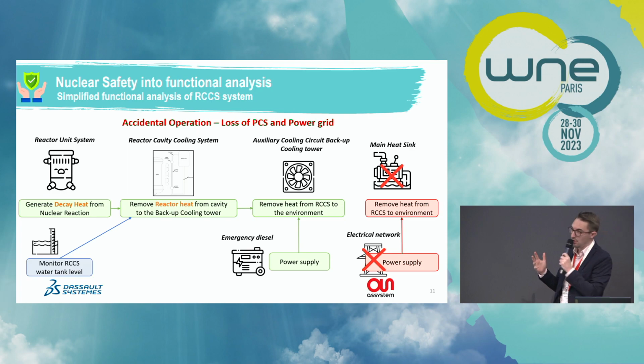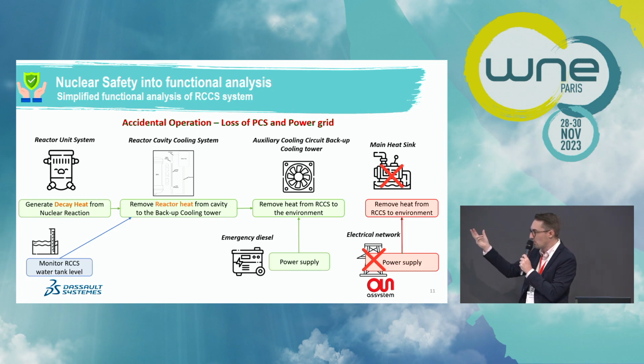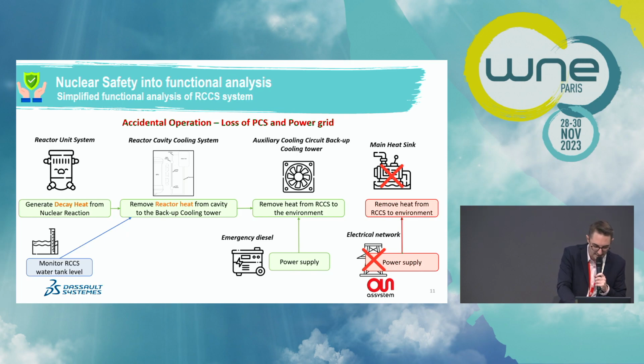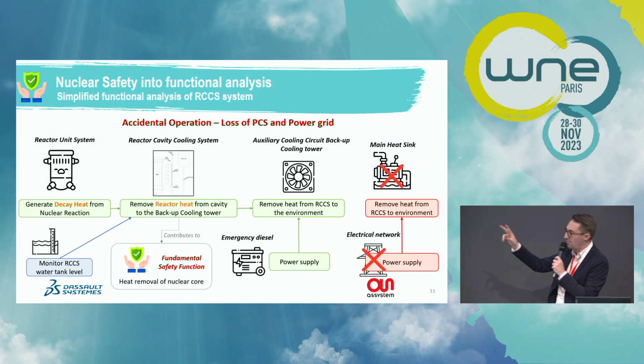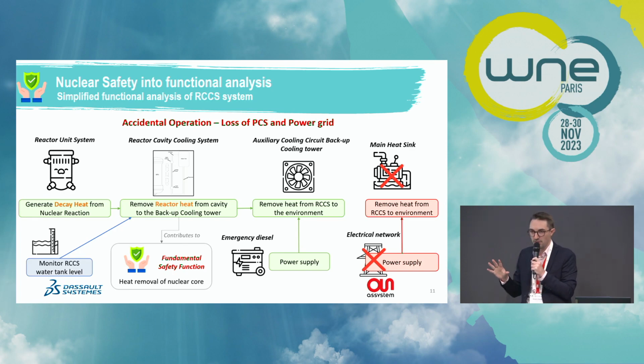To do that, you need a support function: tank level, the water tank level monitoring. This support function allows monitoring of the availability of the safety feature, which is the core heat removal function of the reactor cavity cooling system. This safety feature of the RCCS contributes to the fundamental safety function, which is core heat removal.